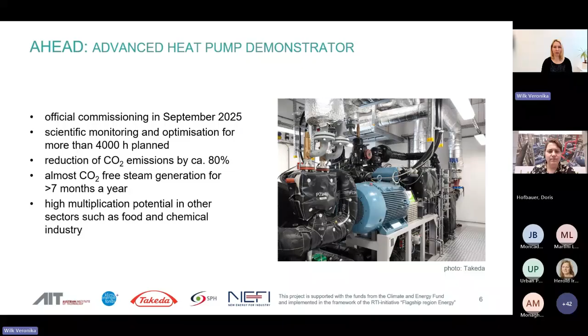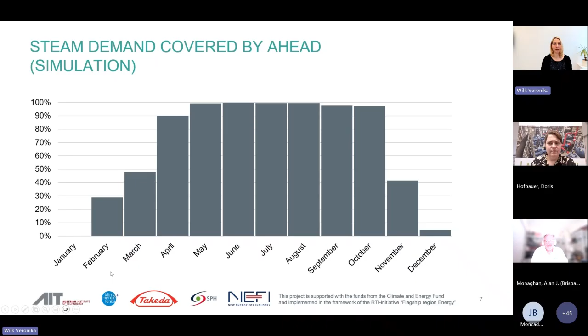Here you see the steam coverage provided by the AHEAD system. From April to October, those are the 7 months where we can almost completely cover the steam demand with the heat pump system. As temperatures decrease in October, November, December, space heating demand becomes more dominant, and there's not enough heat source available to operate the AHEAD system. So it goes out of operation and restarts in February or March, depending on outside conditions. With the monitoring, we will also verify if 2026 looks like the case we see here, which is based on data from 2022.